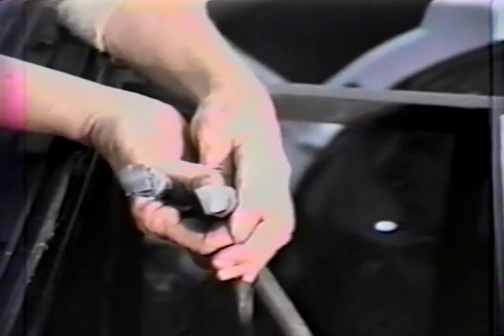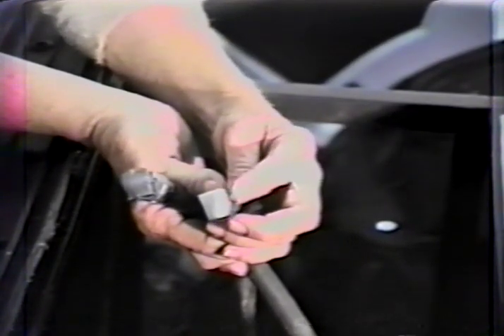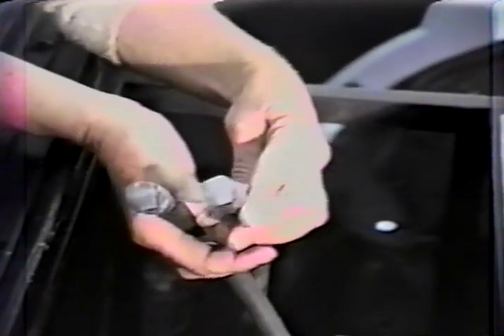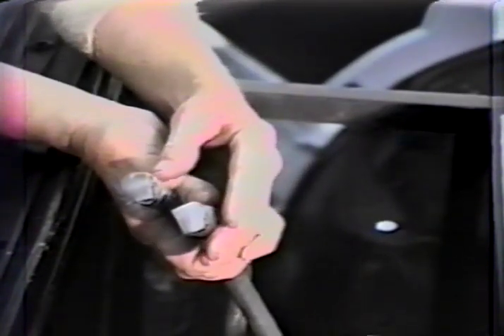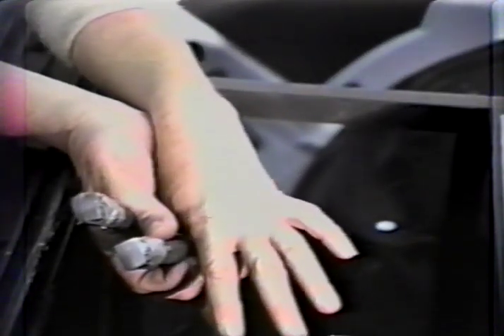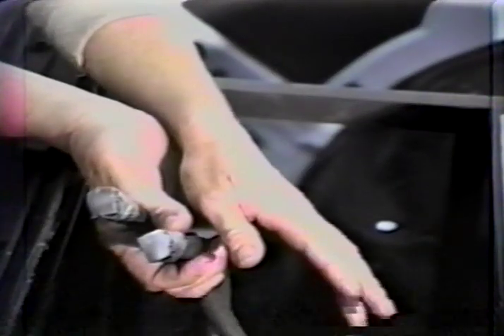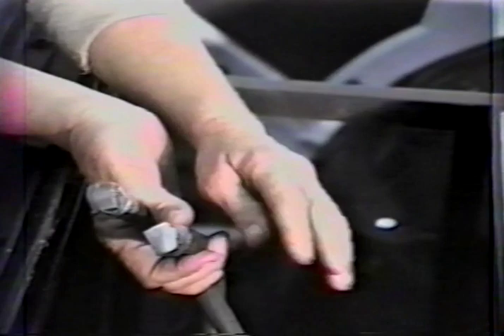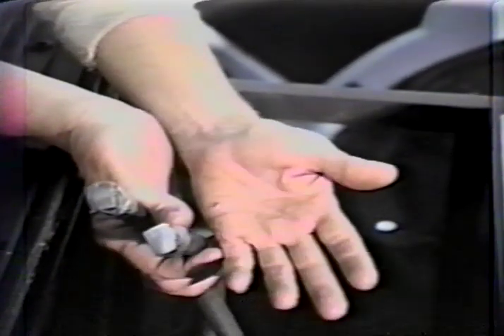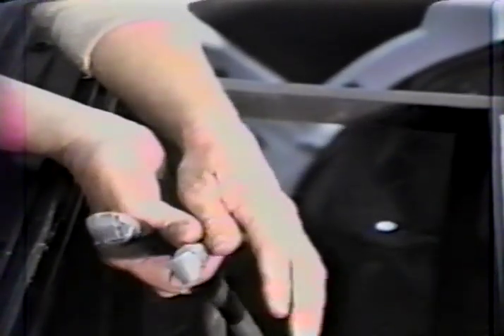One safety note: you may notice the ends of these cables are taped up, and under the tape there's a small piece of neoprene for additional insulation. This is because the batteries are all cabled together in the back, and if these cables touched, it would complete the circuit, which we don't want yet. So to prevent an accident, I have them taped up. That's always a good idea, to make sure nothing connects before you're ready. You may also notice I have no rings, bracelets, or metal watch bands on, because if anything metal accidentally hits some electricity, you could get a bad burn or even amputate a finger. All these safety precautions are very important when working with electric vehicles.